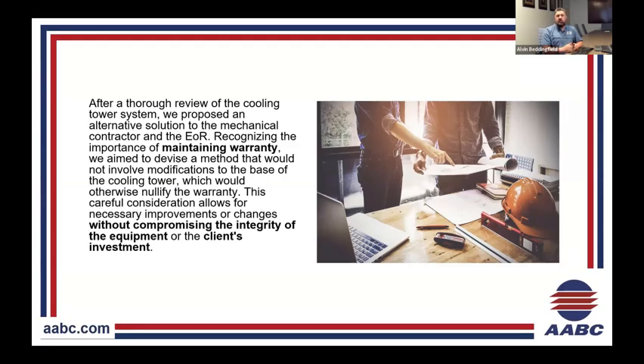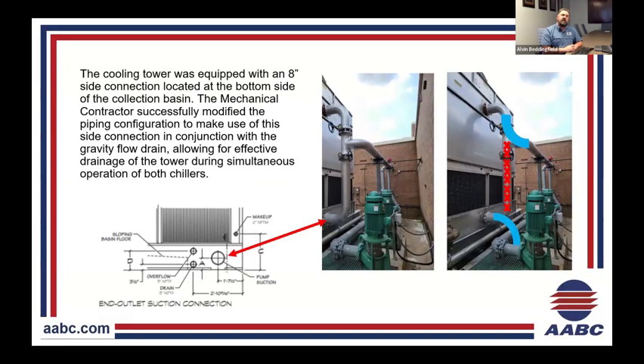So, trying to find an alternative solution to not void a warranty and cause additional headaches to the districts and their investment of the equipment, we had to come up with a solution. So roughly, since we had the supplied end suction connection, right? That was there to begin with. So the snapshot of the picture on the left is how it was installed, right? So obviously the cooling tower was equipped with an additional side 8-inch connection. And the goal was, if we could modify that, reuse that as an additional 8-inch drainage of that tower right back into the sump basin of the concrete basin to avoid penetrating the stainless steel underneath the bottom of the tower.